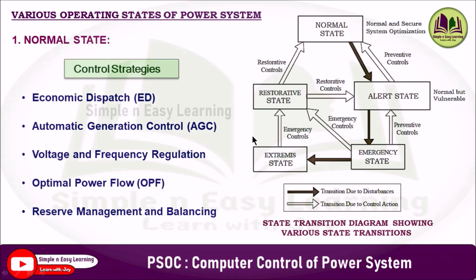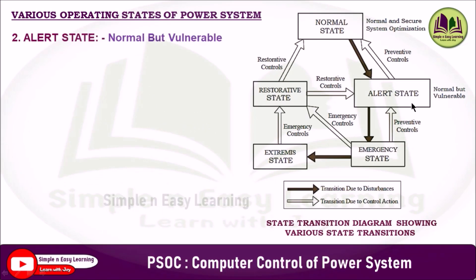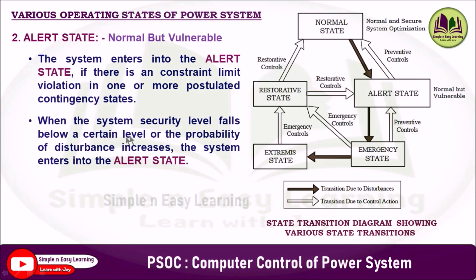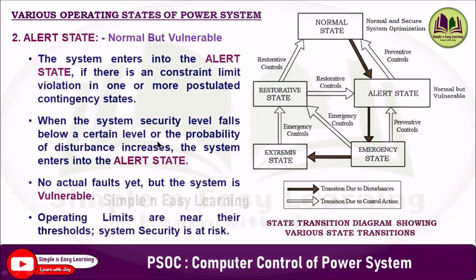The alert state is also a normal state but is vulnerable. The system enters this alert state if there is a constraint limit violation in one or more postulated contingency states. A postulated contingency state is a hypothetical or assumed failure scenario used in system planning and reliability analysis — conditions under which part of the power system is assumed to fail or be removed from service. When the system security level falls below a certain level or the probability of disturbance increases, the system enters the alert state. No actual fault has occurred yet, but the system is vulnerable and operating limits are near threshold values.